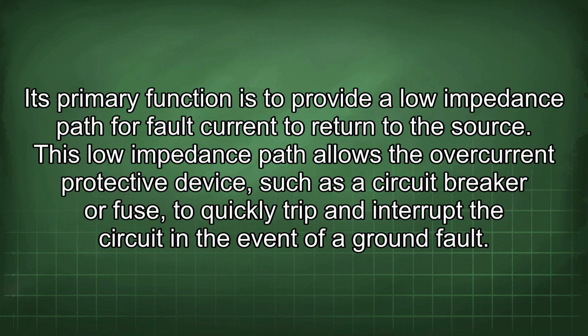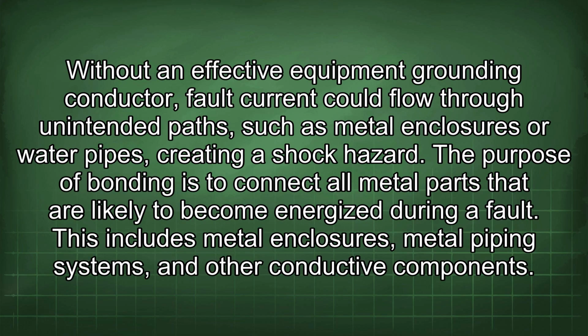Its primary function is to provide a low impedance path for fault current to return to the source. This low impedance path allows the overcurrent protective device, such as a circuit breaker or fuse, to quickly trip and interrupt the circuit in the event of a ground fault.